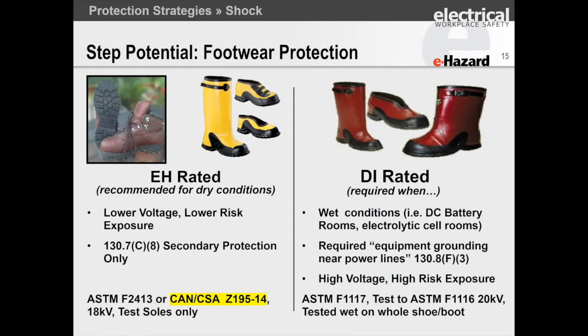EH-rated shoes are definitely a lower level of protection, but they are protection. They're called secondary protection in OSHA, and secondary protection in CSA Z462 and NFPA 70E, but they're critical.